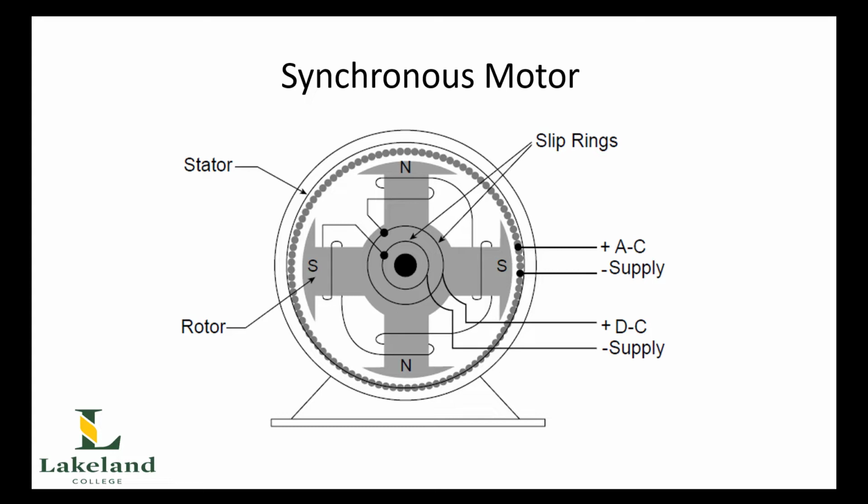But we only excite the rotor winding with a DC supply once we achieve a minimal slip. That basically means that this thing is going to start up as an induction motor. Or we could start it in a variety of different other ways that I'll discuss in just a moment. But at the moment, most of these things start up as induction motors.